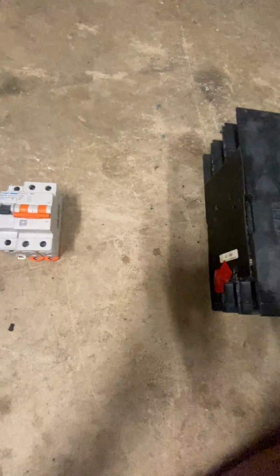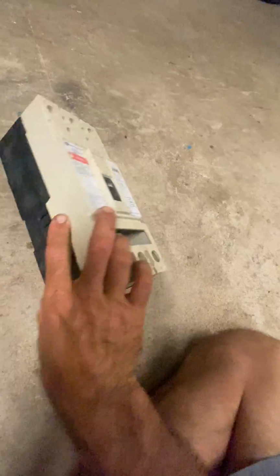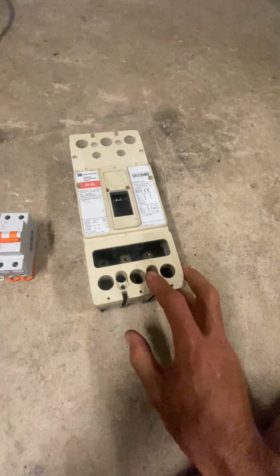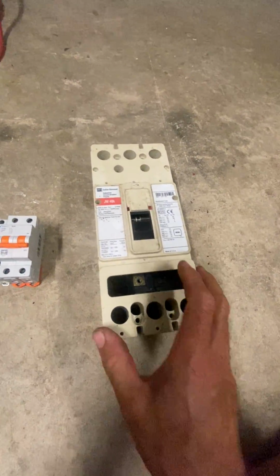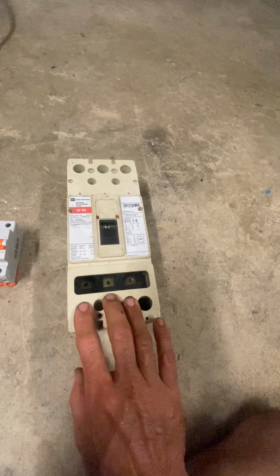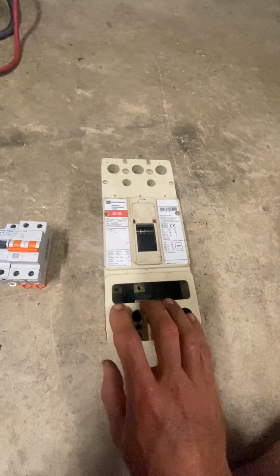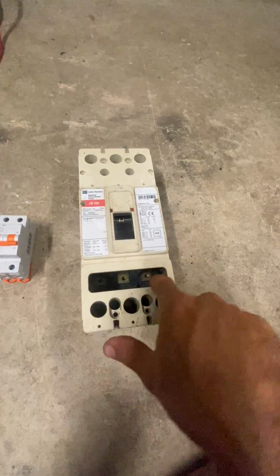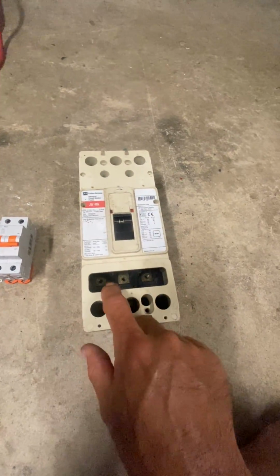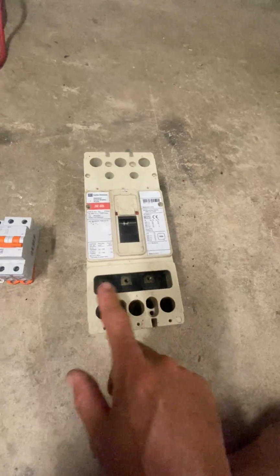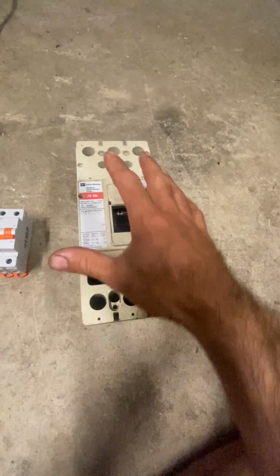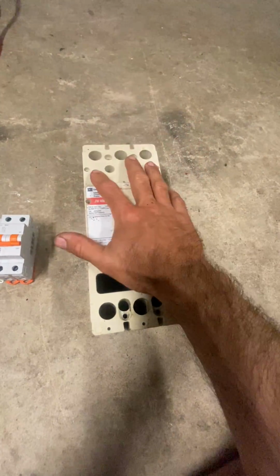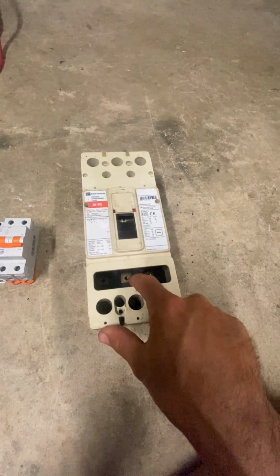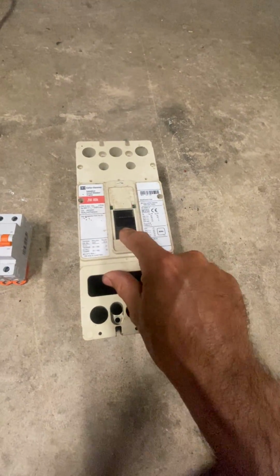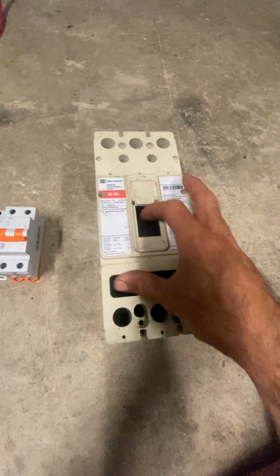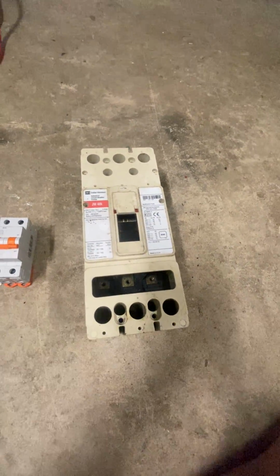So this is normally a bit different mounting in that. So it's designed for a lot more higher current applications, normally like sub-feeds and so forth. And this one is designed so that you can install a shunt device in here to trip based on different conditions. So when you buy these, they come bare like this. Then the shunt is bought separately. This one's actually broken, so it was replaced because the main switch on it broke off after a fault condition.